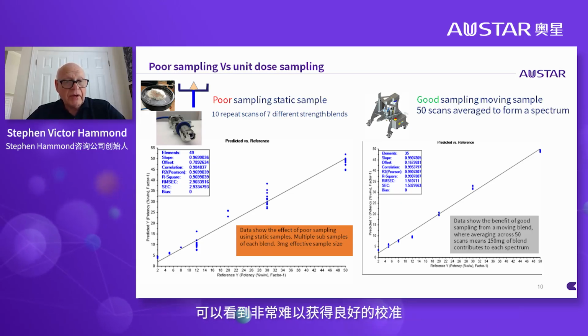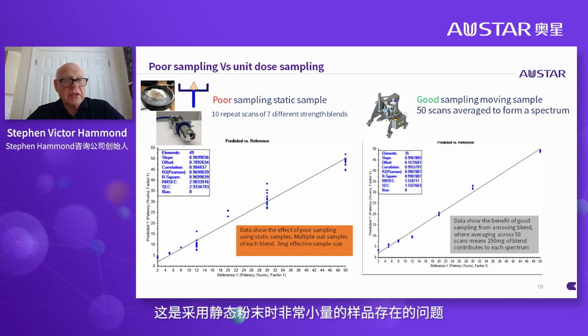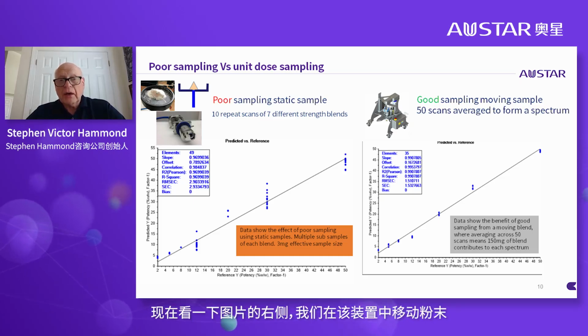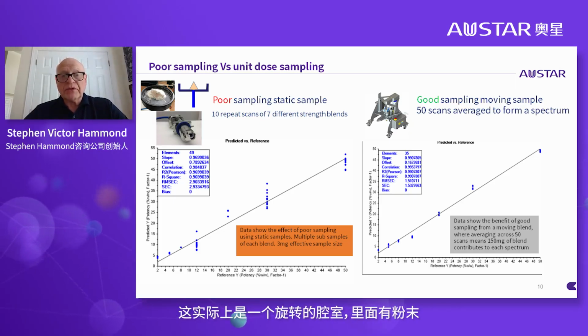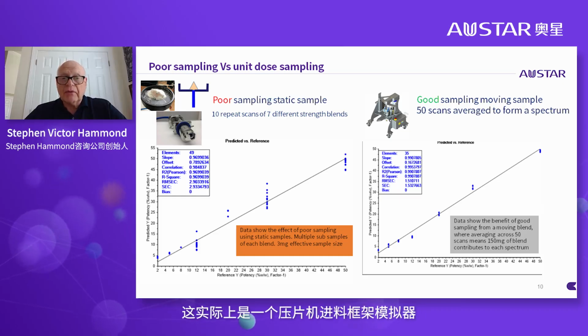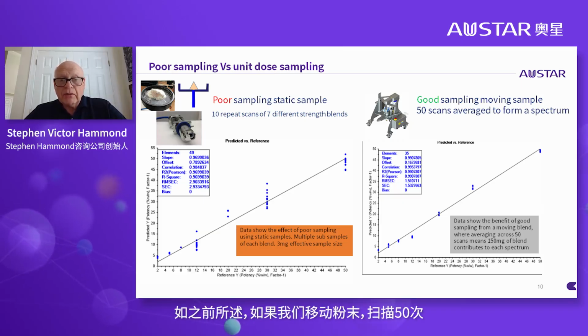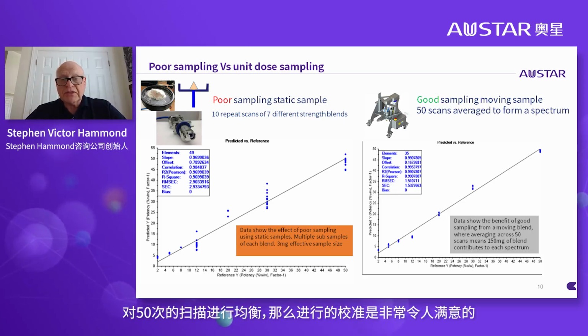And you can see it's very, very difficult to get a good performing calibration. And that really is this problem with very, very small sample size if you have the powder static. Now, if you look at the right-hand side here, where we've moved the powder in this device that is actually a rotating chamber with powder in it, it's a simulator for the feed frame of a tablet press. If we did as I described before, move the powder, scanned 50 times and average those 50 scans, the calibration then built is very high performing and very satisfactory indeed.